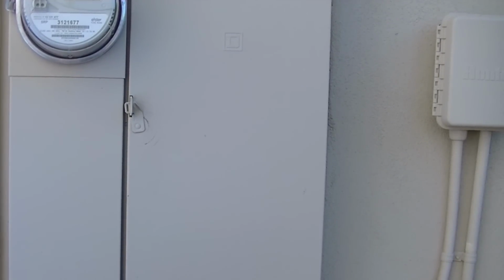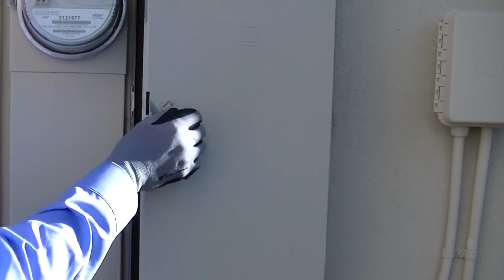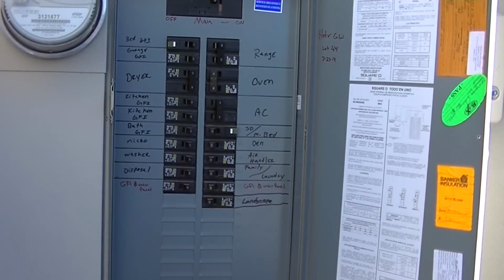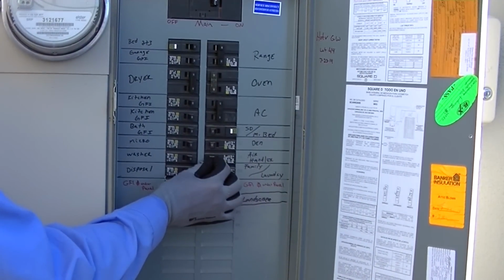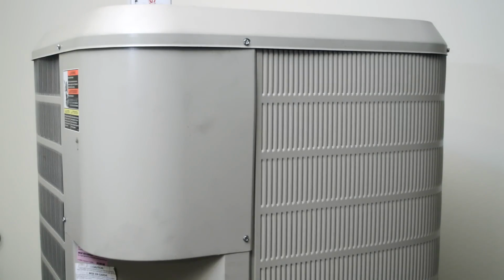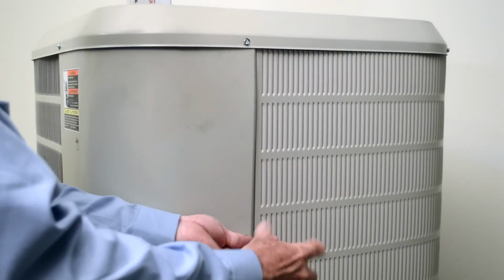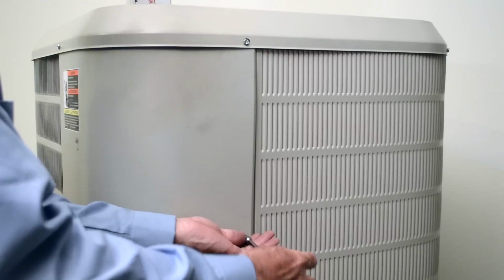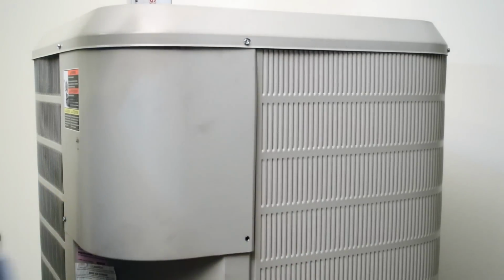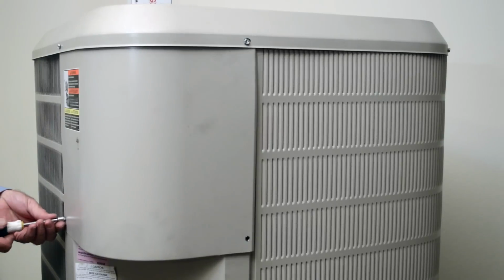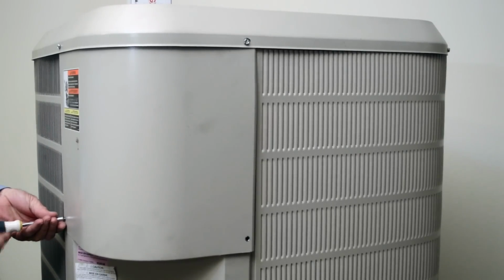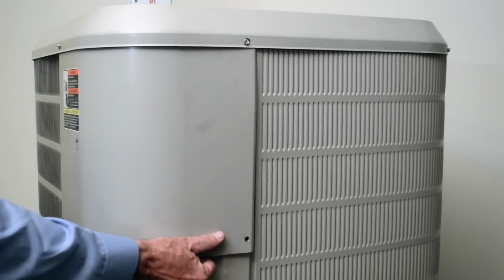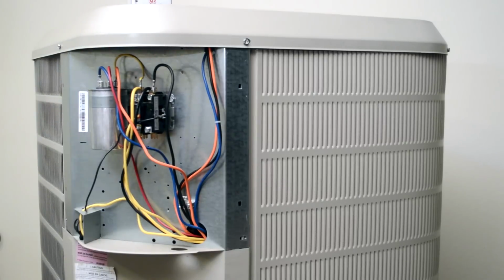positive means of disconnect. Whenever we replace a low voltage control, it's always a good idea to go to the circuit breaker panel and shut off the circuit breaker labeled air handler or furnace to prevent any low voltage shorts. Next, we need to remove the service control panel. We do this by removing the two lower screws at the bottom of the panel with either a 5/16 or a 1/4 inch nut driver. Once these screws have been removed, we simply pull the panel out and down, exposing the components of our condenser.